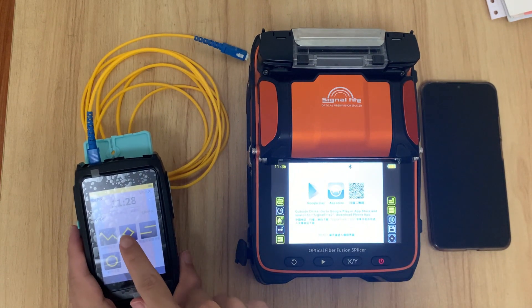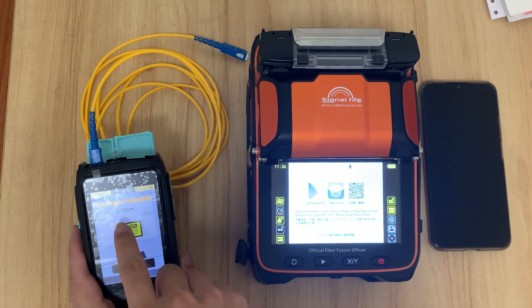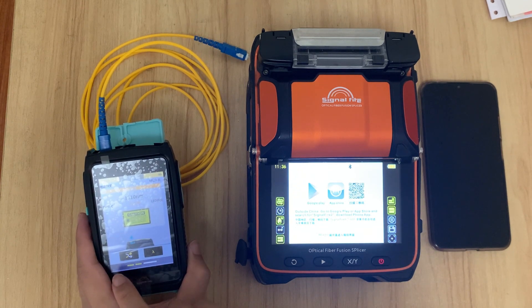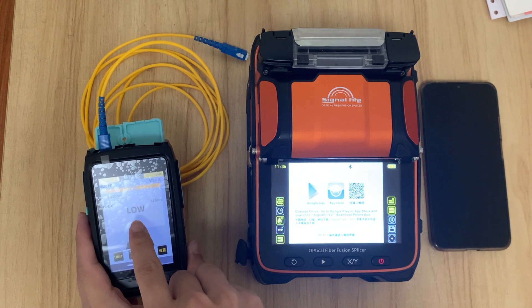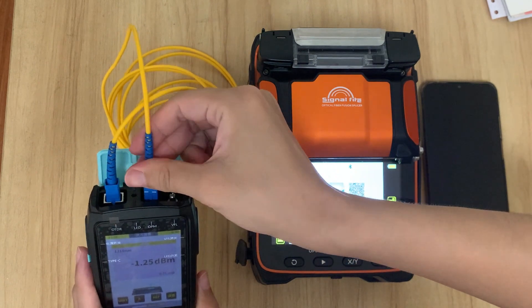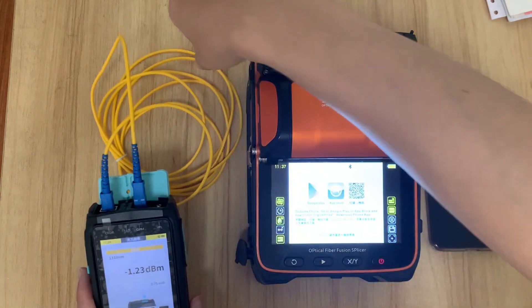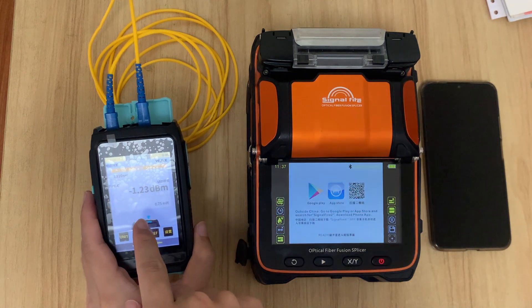The second thing is to select the correct wavelength. You can see that 1310nm is currently turned off — we need to turn it on. Then check the OPM test page, and plug the fiber jumper into the OPM socket.